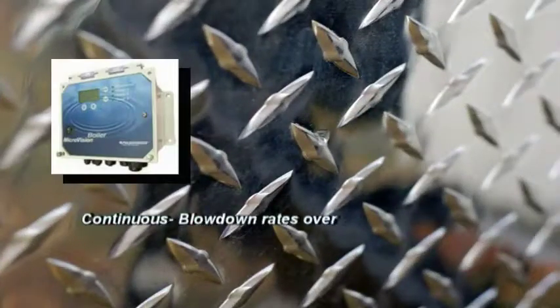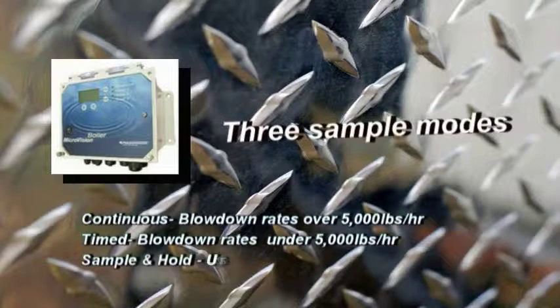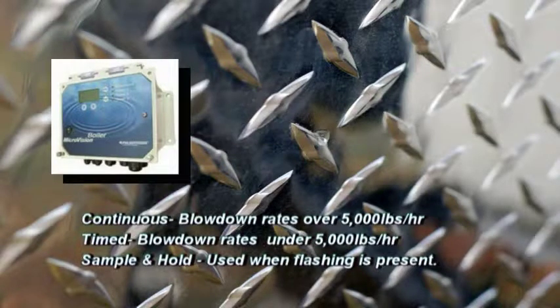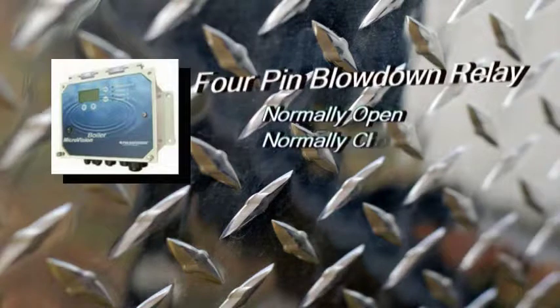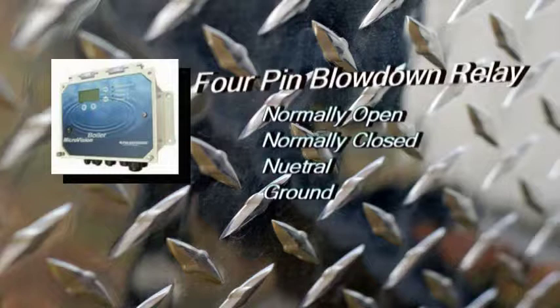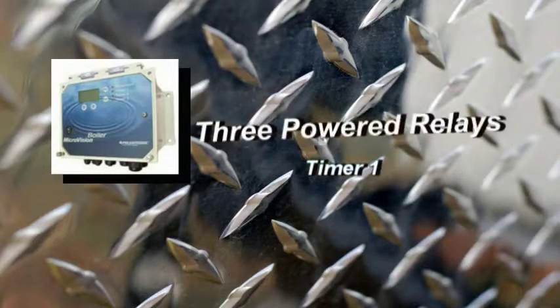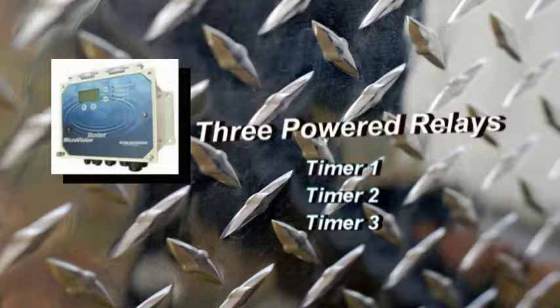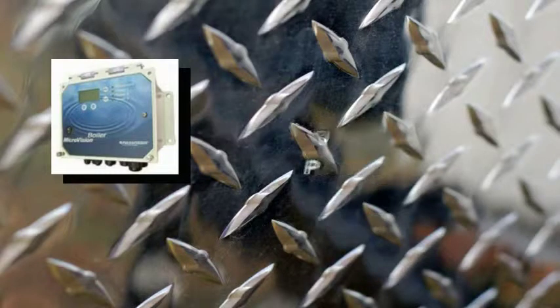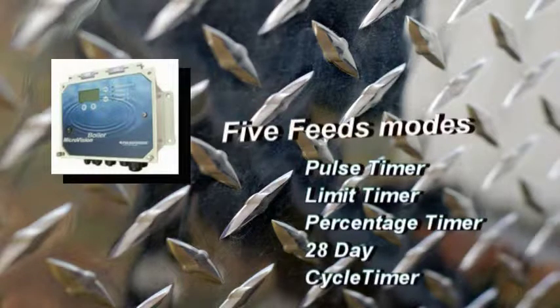The MicroVision Boiler has 3 sampling modes: continuous, timed, or sample and hold modes. The controller comes factory set in the time sample mode with preset set points and differentials. Blowdown control is accomplished with a powered relay that allows for either motorized ball valve or solenoid valve connection. There are 3 powered relays for control of chemical metering pumps. Each has selectable timers with 5 different options.